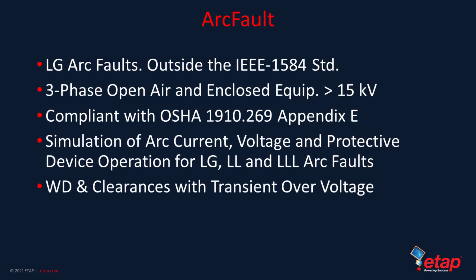Also following the protection and coordination is the ability to do arc flash, especially on some of these locations that are well above 15 kV, which falls outside the IEEE 1584. ETAP's high voltage arc flash module is called Arc Fault and it provides the ability to do line-to-ground arc faults on locations outside of the IEEE 1584 standard — typically locations above 15 kV.